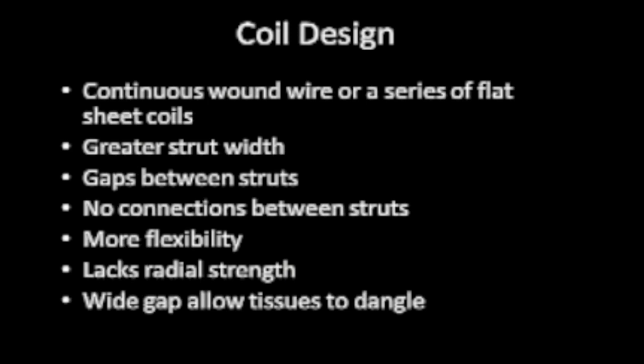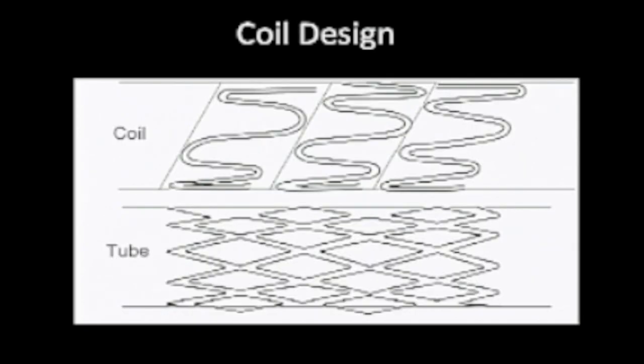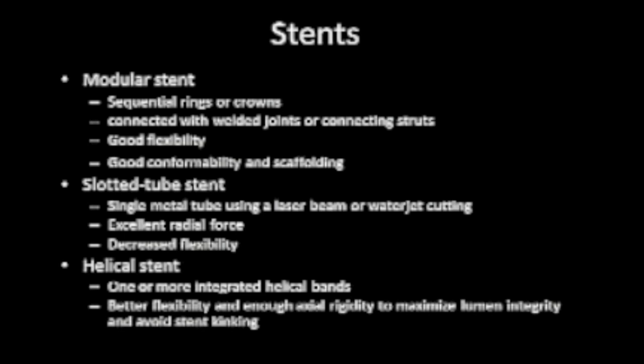There are two groups of stents: coil designs and tube designs. A coil design is a continuous wound wire series of flat coils with greater strut width but no connections between the struts — more flexible but less radial strength, so it can collapse more easily, and there is a wide gap that allows tissues to dangle. There are also all types including modular, slotted tube, and helical stents. The more rigid they are, the less flexible but the more radial force and hoop strength they provide.